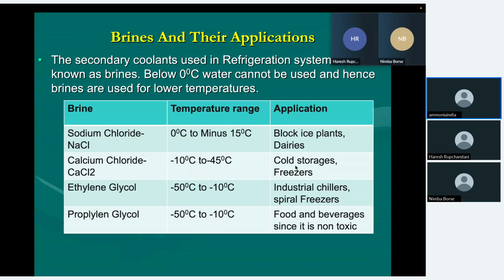For example, in block ice plants, they use ordinary salt as a brine, which can go to a temperature of up to minus 15 degrees centigrade. Dairies and block ice plants use sodium chloride. For a little more advanced systems, calcium chloride, with some agents added to it, is used up to minus 45 degrees centigrade, and is very popular in cold storages, freezers, etc.